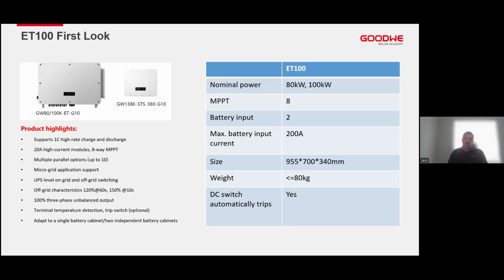The unit supports parallel up to 10 units, so up to 1 meg. Fully support microgrid applications, and it will have UPS level on-grid and off-grid switching. In terms of overloading, it will support 150% overloading for 10 seconds, again to accommodate inrush currents and motor startup applications. And it will adapt to single battery cabinet or 2 independent battery cabinets as well.